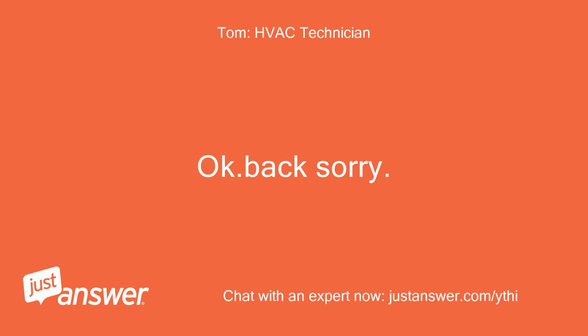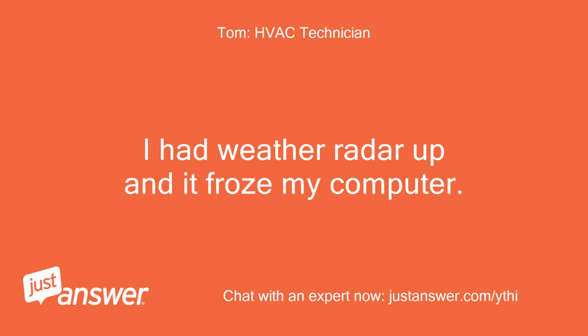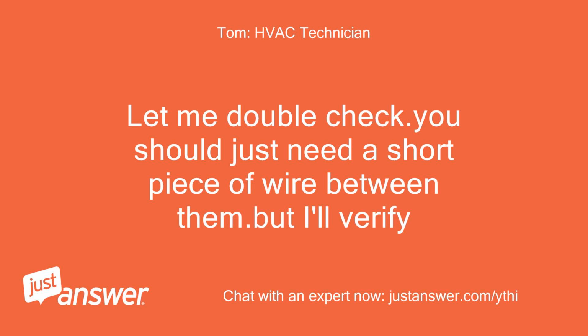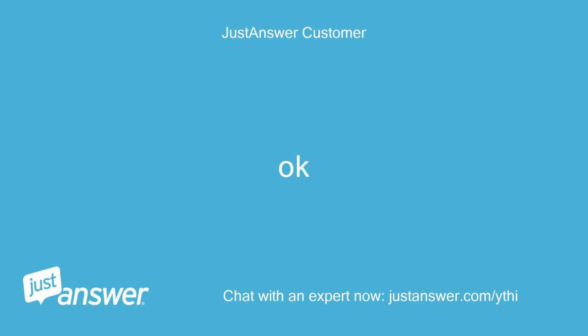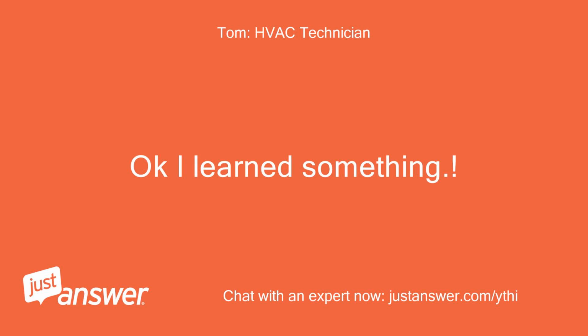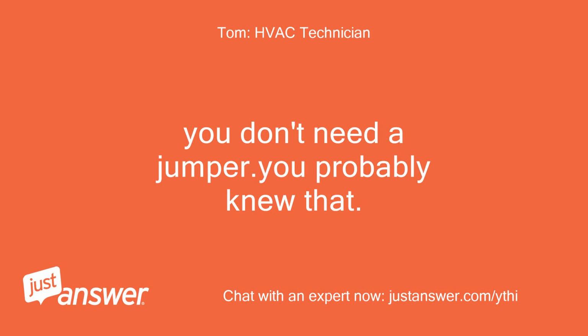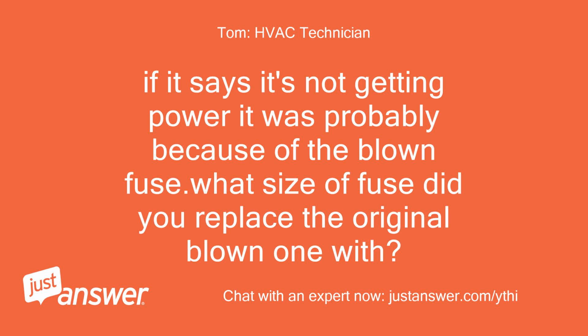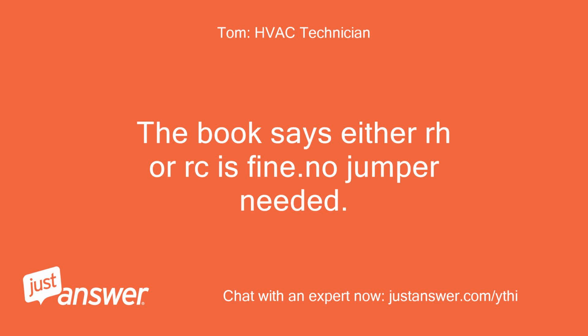Okay. Back, sorry. I had weather radar up and it froze my computer. Let me double check. You should just need a short piece of wire between them. But I'll verify. Okay. Okay, I learned something. You don't need a jumper. You probably knew that. If it says it's not getting power, it was probably because of the blown fuse. What size of fuse did you replace the original blown one with? The book says either RH or RC is fine. No jumper needed.